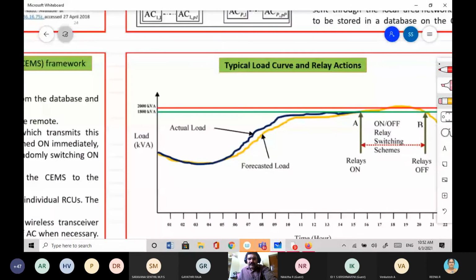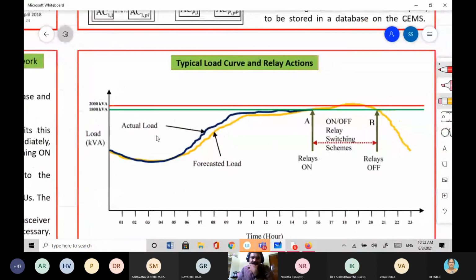If you look at this load curve, you'll understand. This is the 2000 kVA line. If you go beyond this, we pay a penalty. If we cross by 100 units, then 100 into 700 is what we have to pay to TANGEDCO. So what we have done is set 90% of the load in kVA as a threshold.